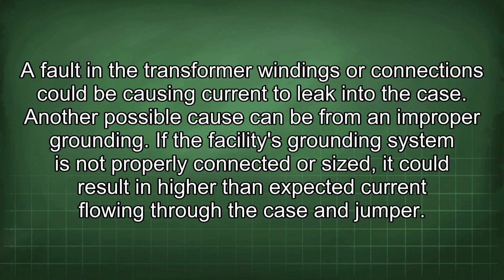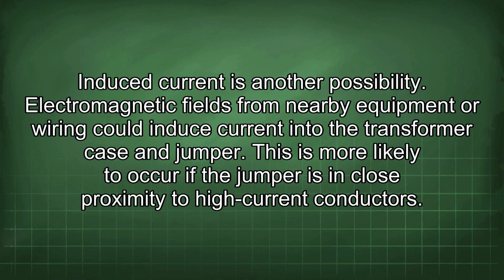Another possible cause can be from an improper grounding. If the facility's grounding system is not properly connected or sized, it could result in higher than expected current flowing through the case and jumper. Induced current is another possibility. Electromagnetic fields from nearby equipment or wiring could induce current into the transformer case and jumper. This is more likely to occur if the jumper is in close proximity to high current conductors.